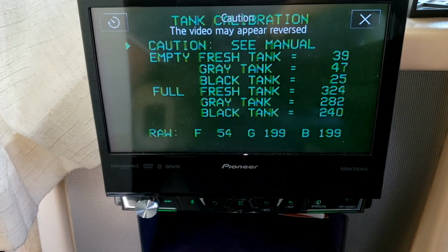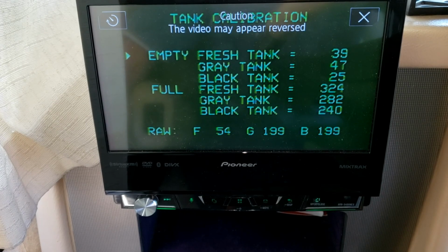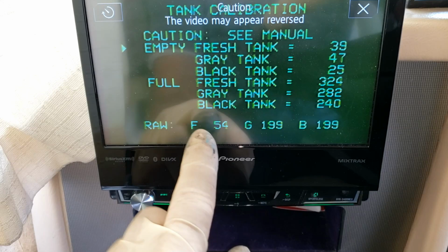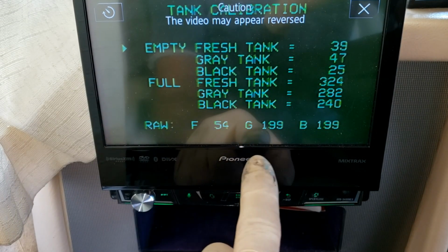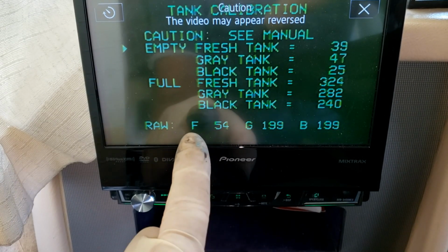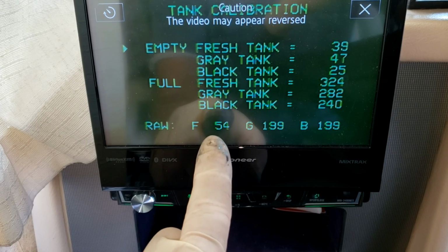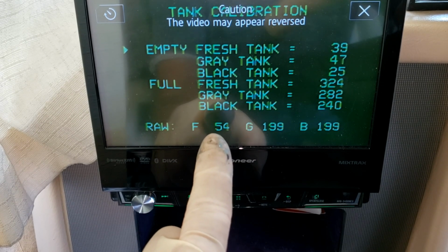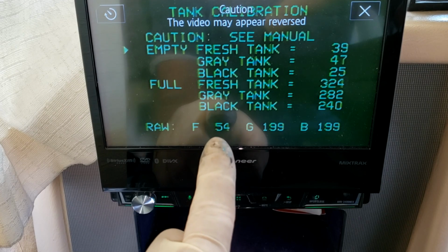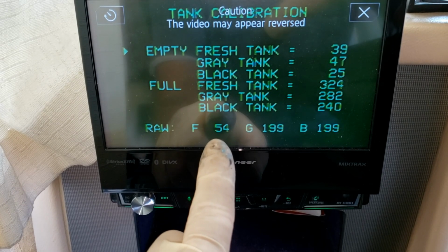We'll go to that one. Now if we go to freshwater tank right there, you see right here, we have the freshwater. This is the raw data straight from those sensors right there. So at empty, that sensor is saying that 54, the value 54, is empty. I don't know if you can see that right now, but it's programmed for 39 being the value of empty.